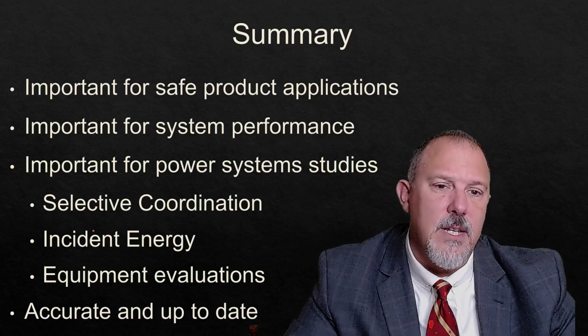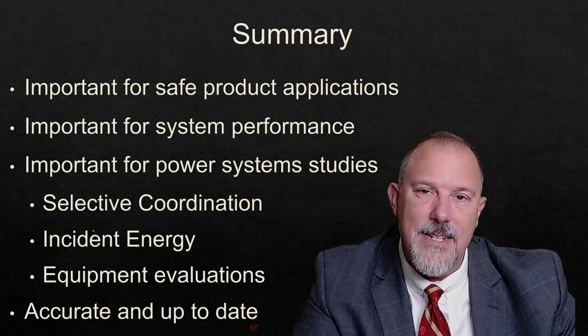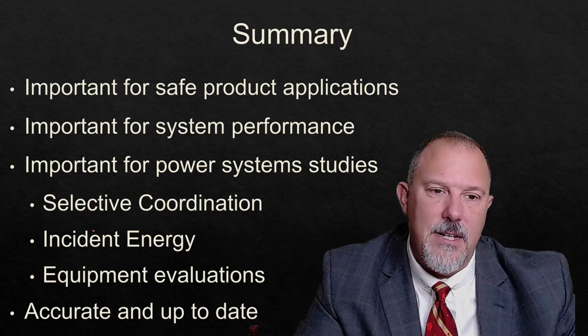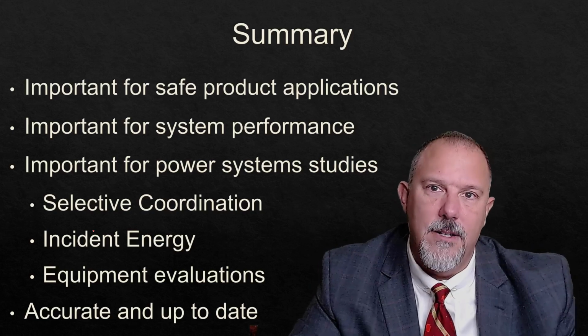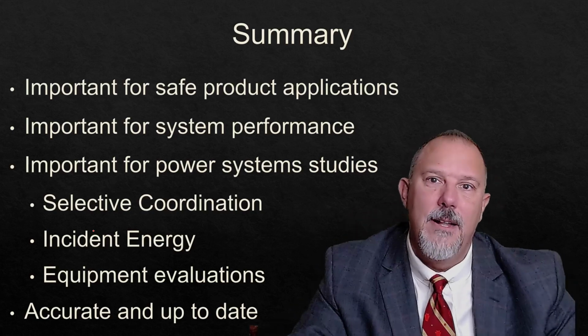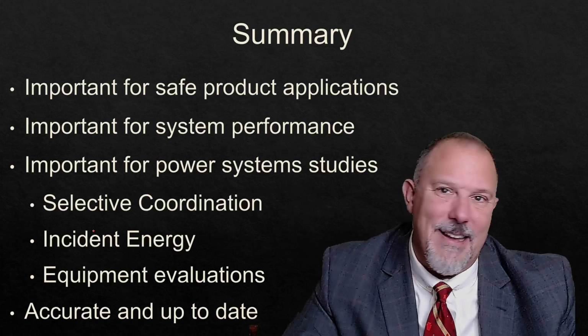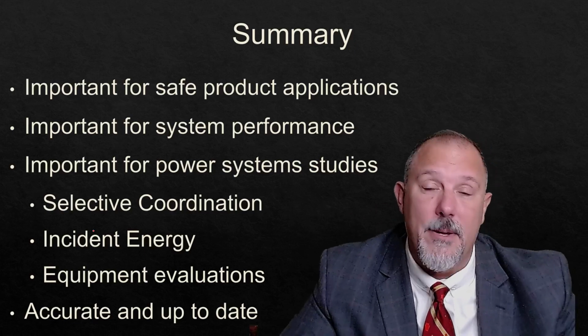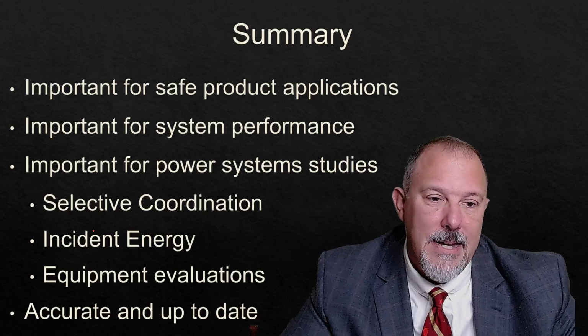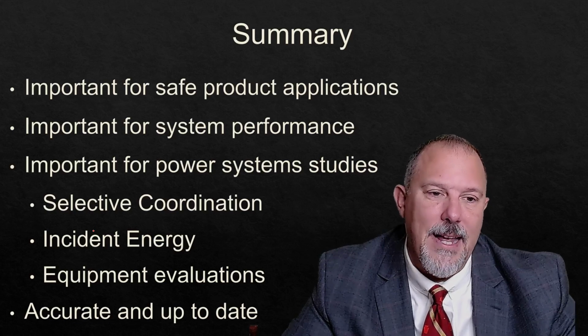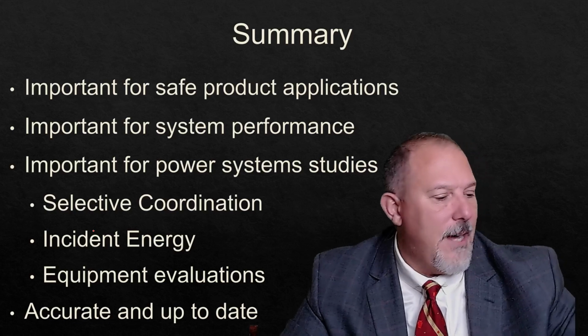Important for power system studies, selective coordination, incident energy. I can't calculate incident energy if I don't know my fault current. I can't calculate my fault current if I don't have an accurate one-line diagram. Please don't forget about the one-line diagram. And if I want to do my equipment evaluations, it all has to be accurate and up to date.